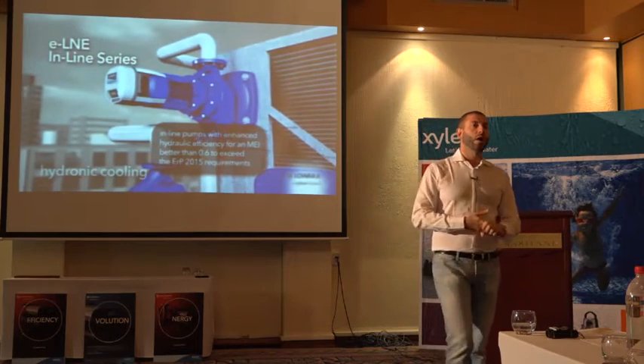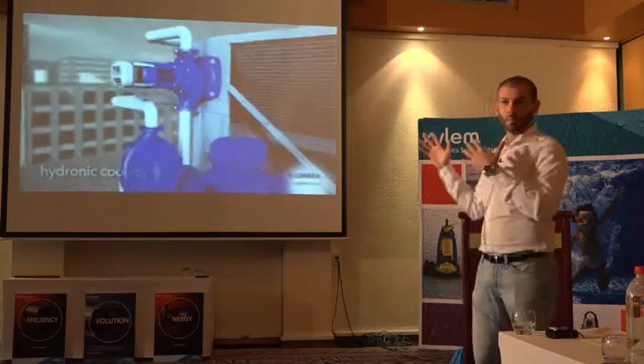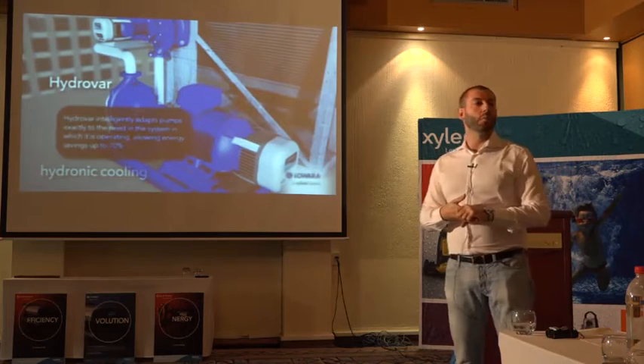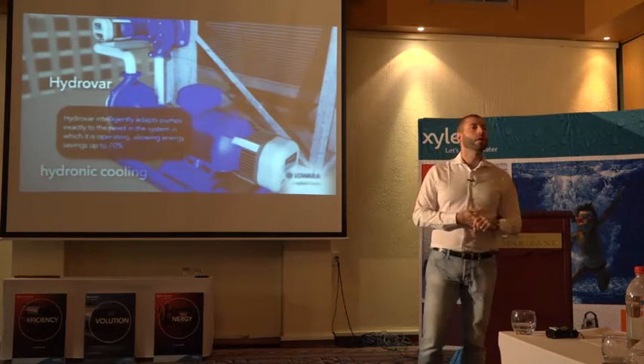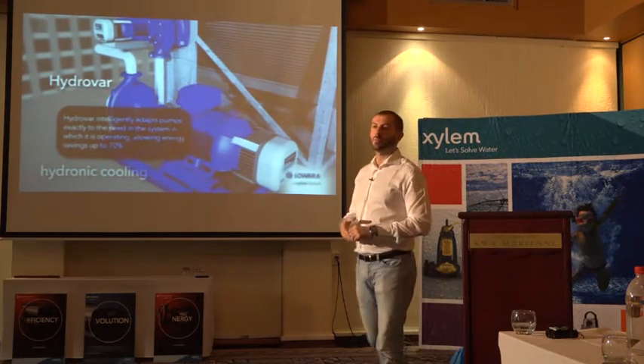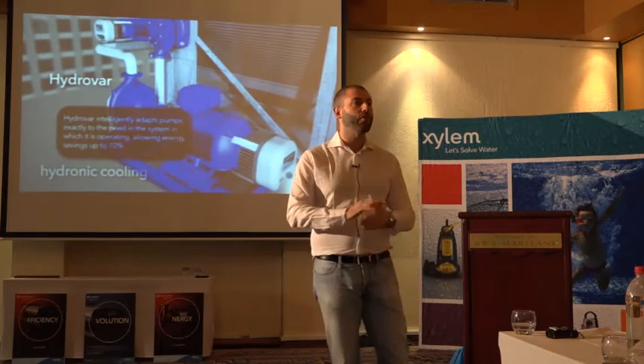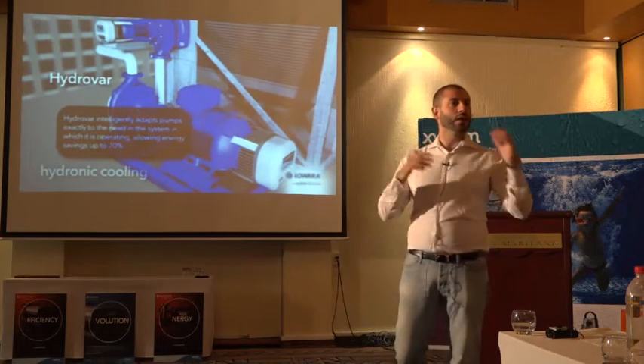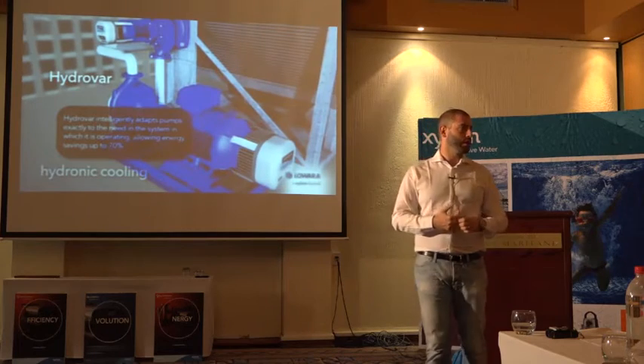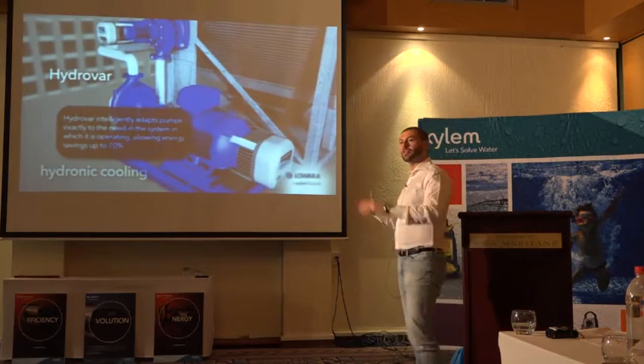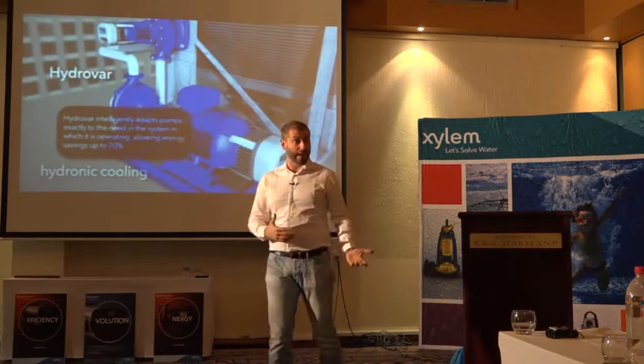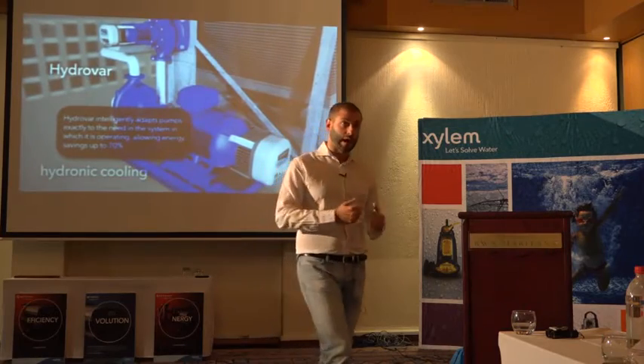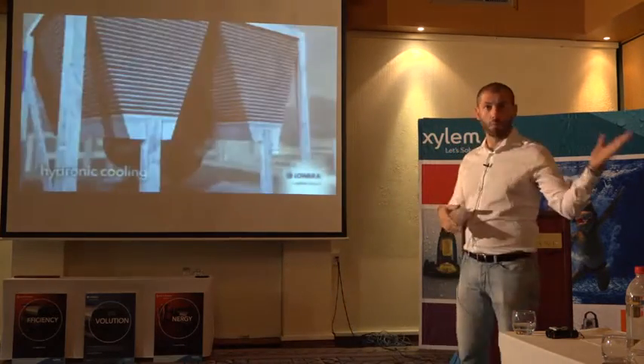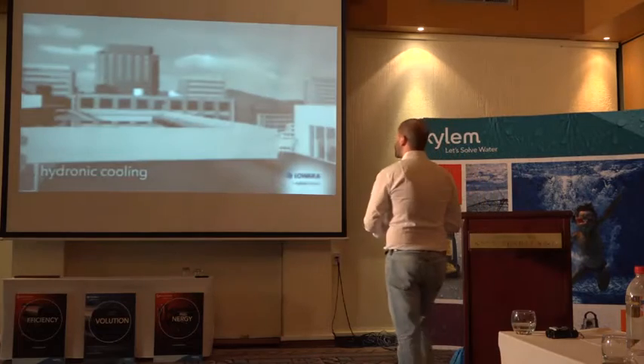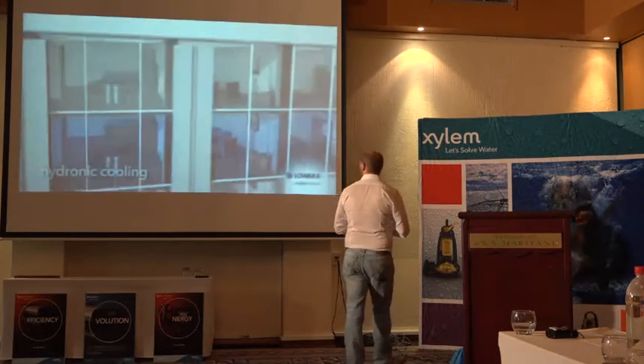As I said on Thursday, this pump as standard is available with a cast iron pump body and cast iron impeller, but you have a complete offering of materials: stainless steel, duplex, and bronze impellers. For the casing, there is cast iron, ductile iron, stainless steel, and duplex, covering from 1 up to 1,800 cubic meters per hour.